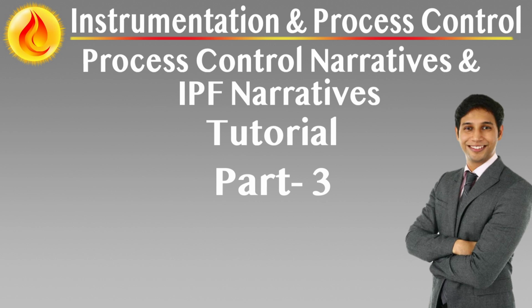Dependencies and configuration particularities highlights any specific configuration features needed to ensure proper system integration, such as control system time synchronization, mode switching logic, e.g. remote local, manual auto, redundancy schemes, and master-slave arrangements. These details are critical for both control vendors and system integrators.